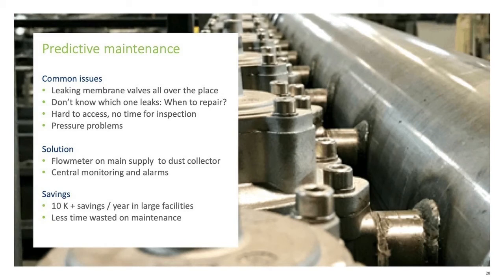In some cases, it's hard to access, and there's no time for inspection because it might be in a tower-shaped construction, or on the roof of a building. But if a couple of these valves start to leak, they will probably cause a lot of air demand and maybe also some pressure problems in equipment nearby. So the solution is to measure flow in the main supply to the dust collector, connect that to a central monitoring system and put some alarms on it. In that way, you will be ahead of the problem, or at least on the problem when it occurs, instead of letting it go for months or even years.